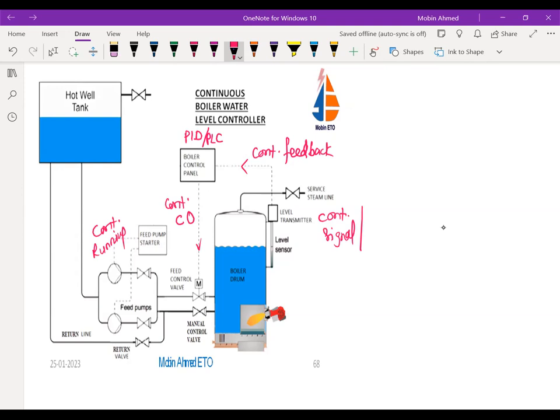Now, if this feed control valve has an issue, or anything in the closed loop system, like the sensor has failed, or the PID or PLC is not working, then for redundancy or emergency purposes we have this manual control valve. So we are going to control the level with this. We just open it on a trial and error basis and adjust the level. Then we need to watch it continuously.